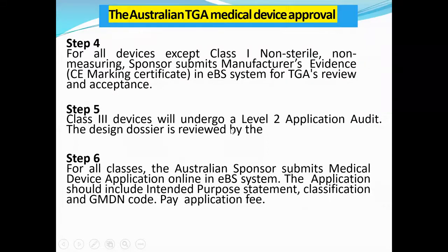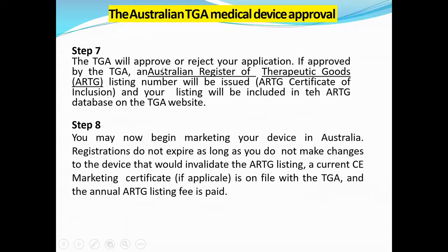Then class 3 devices will undergo a level 2 application audit, and the design dossier is reviewed by the authority. Then for all classes, the Australian sponsor submits the medical device application online in the EBS system. The application should include the intended purpose statement, classification and GMDN code, and the application fee is paid. Then the TGA will approve or reject your application. If approved by the TGA, an ARTG listing number will be issued, and your listing will be included in the ARTG database on the TGA website.